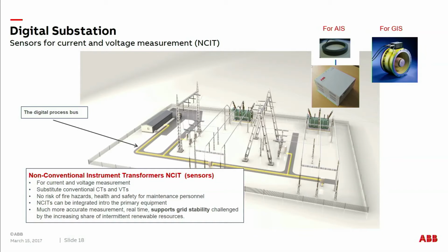Today, the output is a couple of amps and around 100 volts to measure current and voltage. That will not be needed anymore. You can then basically measure in millivolts or milliamps, microamps. So this is a completely different level. But then you cannot transport these measurement signals a couple of hundred meters through a substation anymore. Then you have to digitize it immediately at the sensor, meaning that at the sensor you will also have a piece of electronics. And this is exactly what you see here.